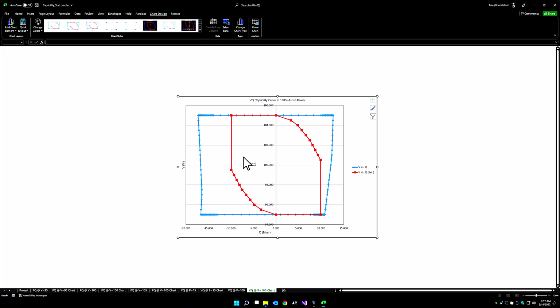So the grid code assessment lets you automate these sweeps of voltage and real power and determine whether you are within compliance within the given PQ capability limits, as well as low voltage and high voltage ride-through limits provided by the grid at the point of connection. With grid code analysis and the automated assessment, it's the most important tool that you need in your toolbox in order for you to perform any grid interconnection studies from a steady state, transient, and harmonics perspective.